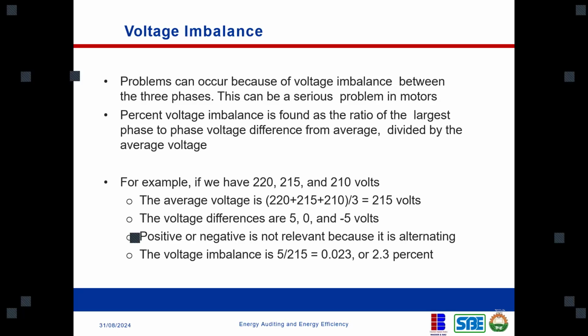If you go to some facilities, you might find that some lines or cables are overheating, especially with a three-phase connection. You can notice that maybe either the red phase, the blue phase, or the yellow phase is overheating. Those are clear indications of voltage imbalance, and you need to check the load distribution across these phases, and then you have to balance it.